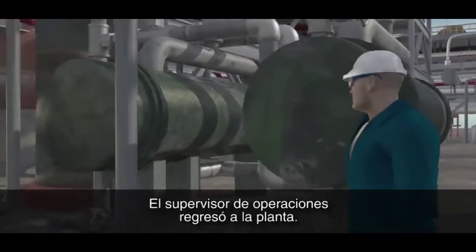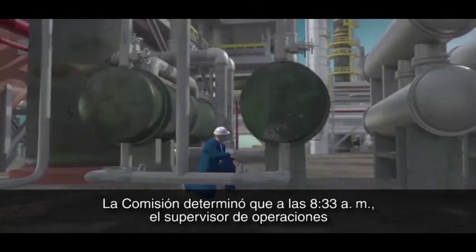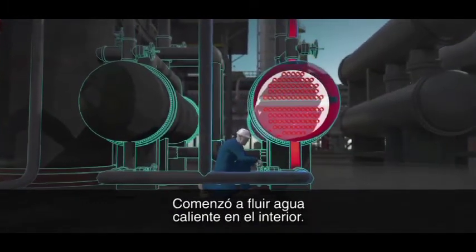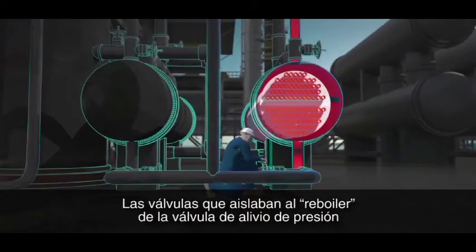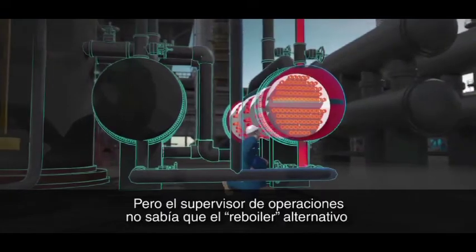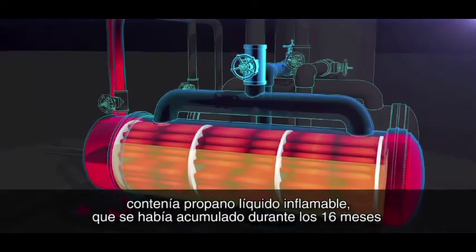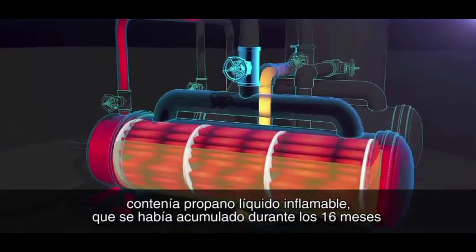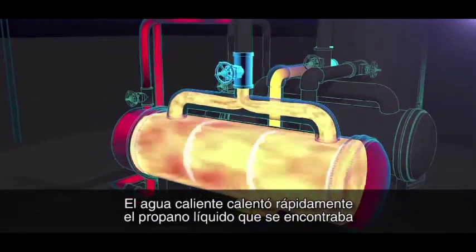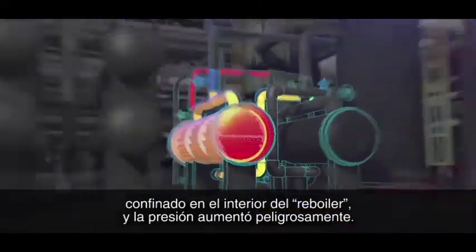The operations supervisor returned to the field. The CSB determined that at 8:33 a.m., the operations supervisor likely opened the water valves on the standby reboiler. Hot water began flowing inside. The valves blocking the reboiler from its protective pressure relief valve remained closed. But unknown to the operations supervisor, the standby reboiler contained flammable liquid propane that had accumulated during the 16 months the reboiler was out of service. The hot water quickly heated the liquid propane confined inside of the reboiler, and pressure dangerously increased.